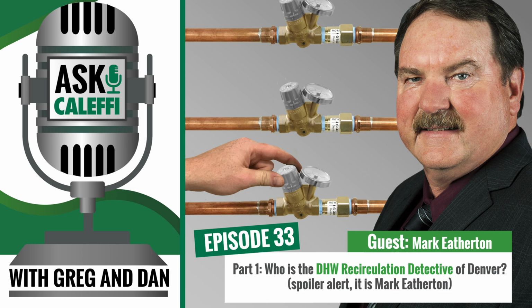You've got a cross-connected shower valve. There's certain types of cartridge shower valves that will cross-connect between the hot and the cold water line. So as people are trying to draw hot water upstream or above that particular cross-connection, the cold cross-connects into the hot and dilutes the hot water that's going up into that riser. So you could have 130 degree Fahrenheit water on the first floor, and when you get to the second floor, you still got 130 degrees, but when you get to the third floor, you can't get more than 90. That's because it's mixing on the second floor. Right.